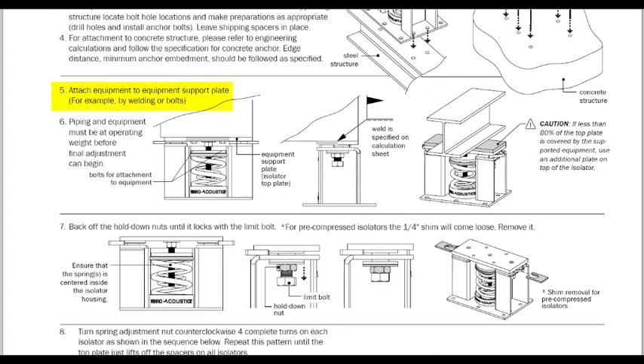Instruction 5 says to attach the equipment to the support plate, for example with welds or bolts. The datasheet gives the size and location of bolt holes in the top plate should they choose to bolt, and the graphic here says that weld is specified on calculation sheet. However, this project was an isolation-only order, and no calculations were done. For any outdoor equipment, it is imperative that they be adequately attached to withstand code-mandated wind loads. We'll definitely want to make sure that the equipment is either bolted or welded to the top plate.